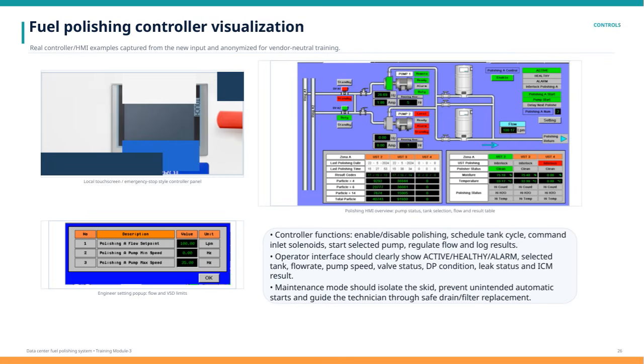The polishing HMI provides a comprehensive overview, showing pump status, tank selection, flow rates, and a results table to monitor performance closely. Engineers have access to a settings pop-up, where they can adjust flow and variable speed drive limits to optimize system operation. The controller functions themselves are quite robust. They enable or disable polishing, schedule tank cycles, command inlet solenoids, start the selected pump, regulate flow, and log all results for accurate tracking. From the operator's perspective, the interface clearly displays key statuses such as active, healthy, or alarm conditions, while also indicating the selected tank, flow rate, pump speed, valve status, differential pressure, leak status, and ICM results, ensuring full visibility at a glance.